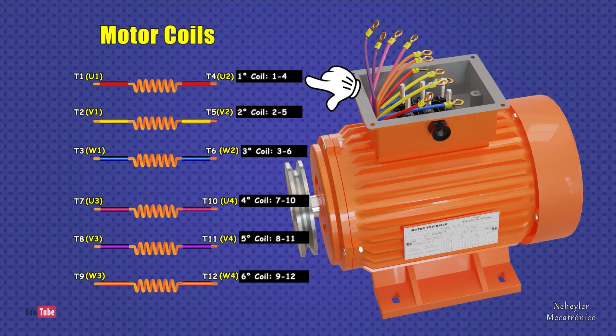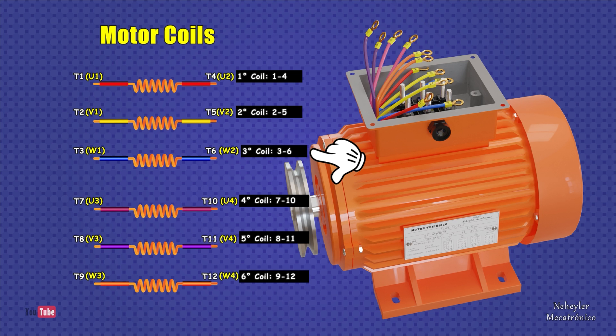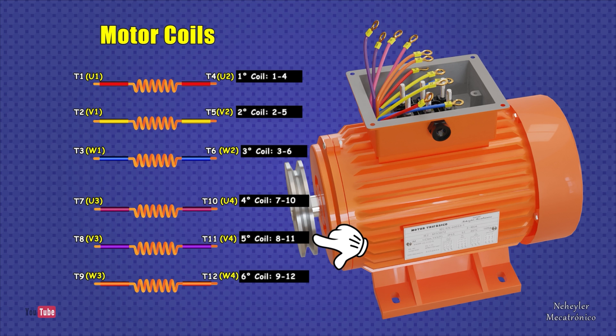The first coil is designated terminals 1 and 4. The second coil is designated with terminals 2 and 5. The third coil is designated with terminals 3 and 6. The fourth coil is designated with terminals 7 and 10. The fifth coil is designated with terminals 8 and 11. The sixth coil is designated with terminals 9 and 12.